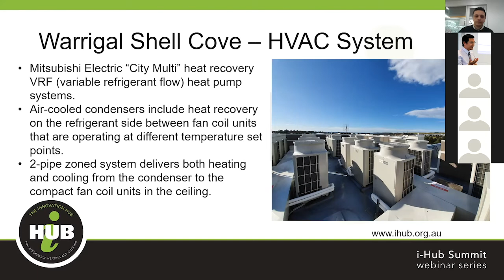For delivering fresh air, most of this is done through an enthalpy recovery ventilator, which delivers fresh air into the corridors, but they also have operable windows. This is controlled by 2 Mitsubishi AE200 HVAC controllers, but every single room also has its own individual wall-mounted unit, and occupants can set their ideal temperature within a band, which shifts depending on summer or winter. This is an interesting area we're looking at within the lab.